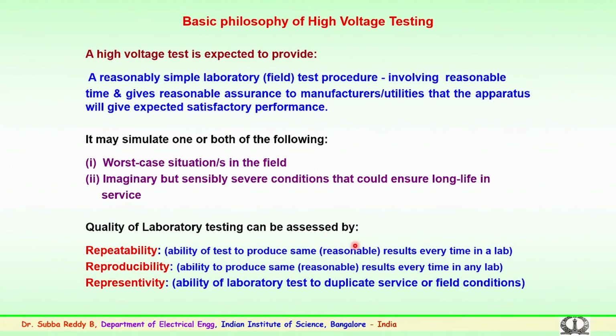Repeatability is the ability of a test to produce the same or reasonably the same results every time in the lab. This indicates that when a particular test is conducted at a different instant of time, at a different period of time, the results produced should be reasonably very near to the values obtained earlier. So, this shows the repeatability of the laboratory equipment which is being used for testing the equipments.